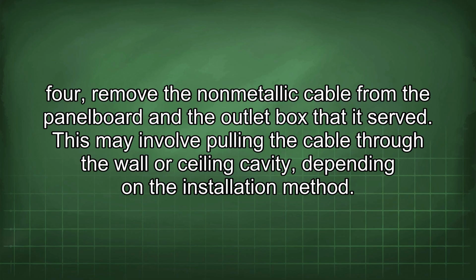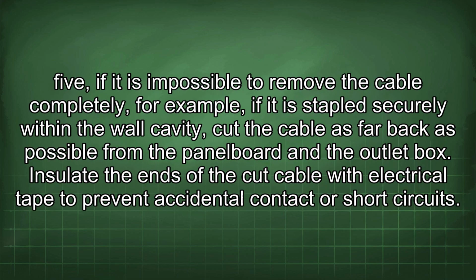4. Remove the non-metallic cable from the panel board and the outlet box that it served. This may involve pulling the cable through the wall or ceiling cavity, depending on the installation method. 5. If it is impossible to remove the cable completely, for example, if it is stapled securely within the wall cavity, cut the cable as far back as possible from the panel board and the outlet box. Insulate the ends of the cut cable with electrical tape to prevent accidental contact or short circuits.